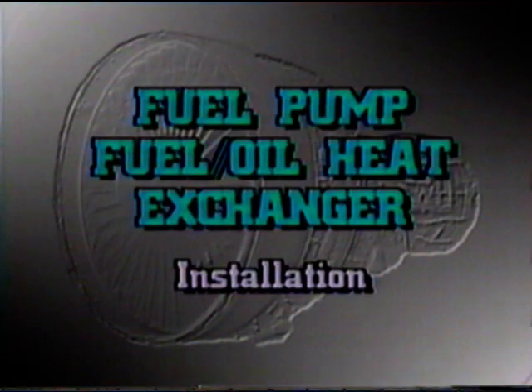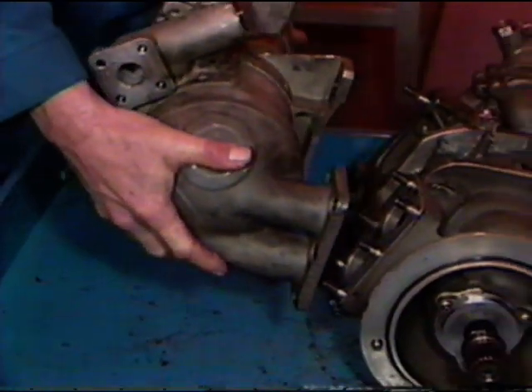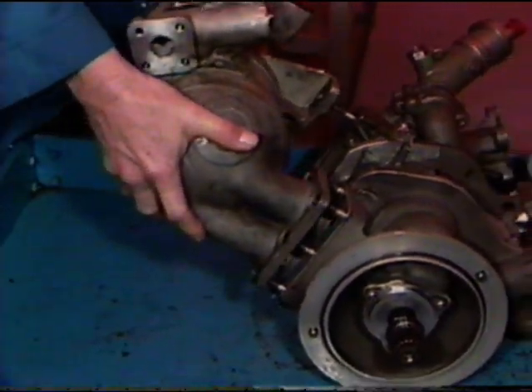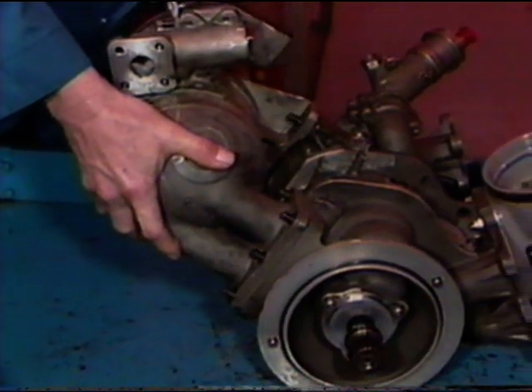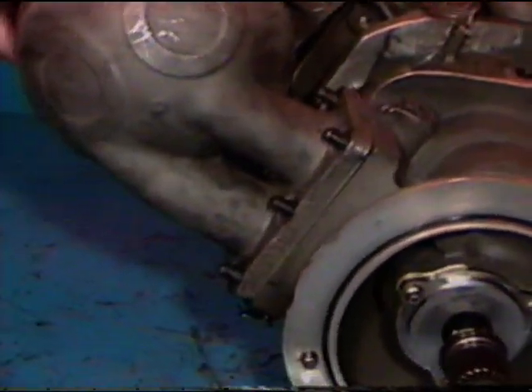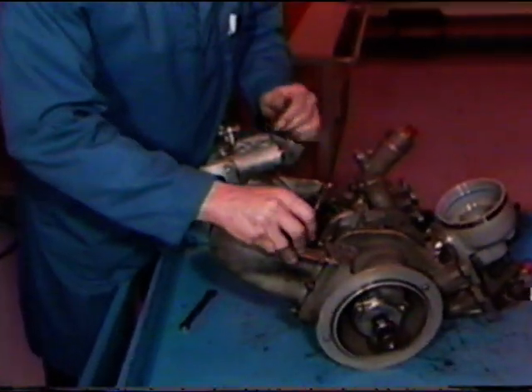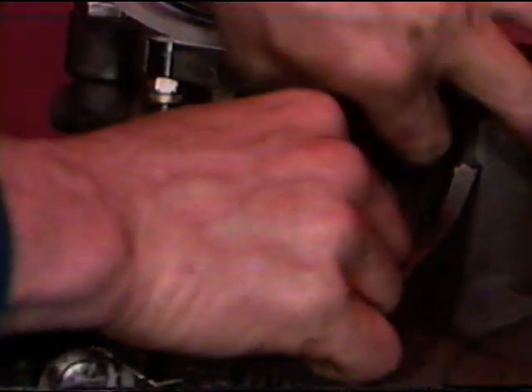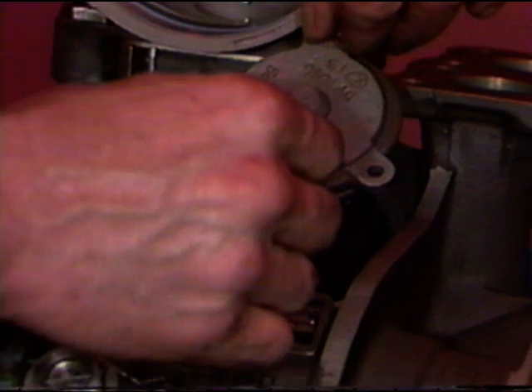Fuel pump, fuel oil heat exchanger installation. Install the gasket and then the heat exchanger on the studs of the fuel pump. Secure it with the washers and nuts. Tighten and torque them to the recommended limit. Then, after removing the 3 bolts that hold the strainer cartridge assembly, use the jack screws and remove the screen. After cleaning the screen, reinstall the cartridge.